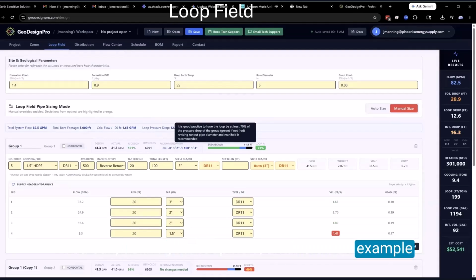Here's an example: we've got 5 bores of 1.5-inch pipe, DR11, going 500 feet deep with a reverse return manifold. We've got 20 feet of tap spacing between the loops, and a total length of run-out pipe going out to the middle of the reverse return manifold. We always ask you to go to the middle of the manifold, because the supply pipe is probably going to be shorter, but the return pipe is going to be longer. That's a length from the interior valve manifold, whether it's in a vault or in a mechanical room. So you specify that length, and specify the diameter.